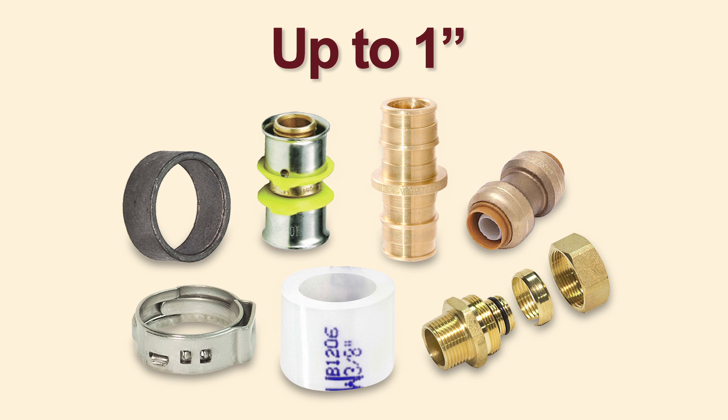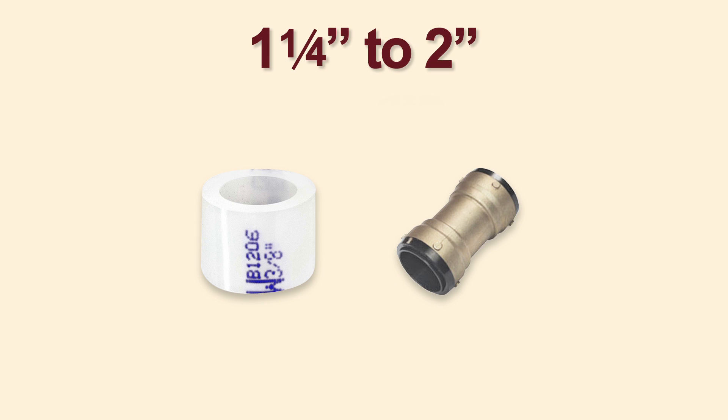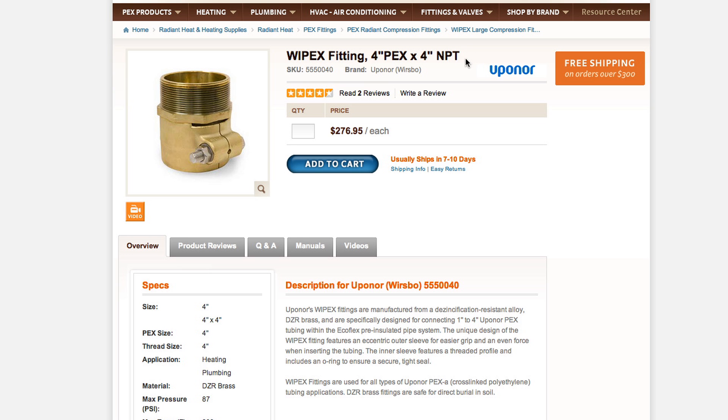All types of PEX connections work with Hepex tubing up to 1 inch, but only Propex expansion fittings and SharkBite fittings work with connections from 1 1/4 inch to 2 inches. For larger sizes you can use Uponor's WIPEX fittings.